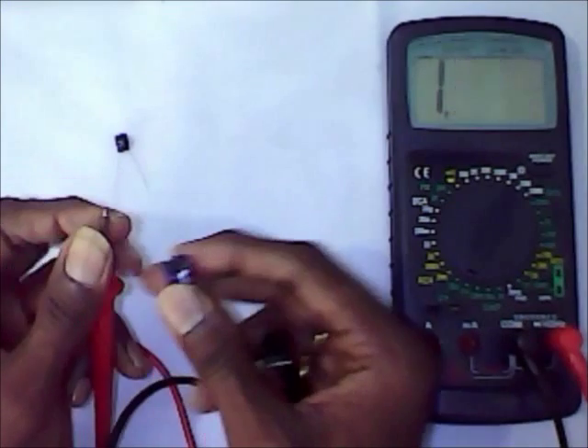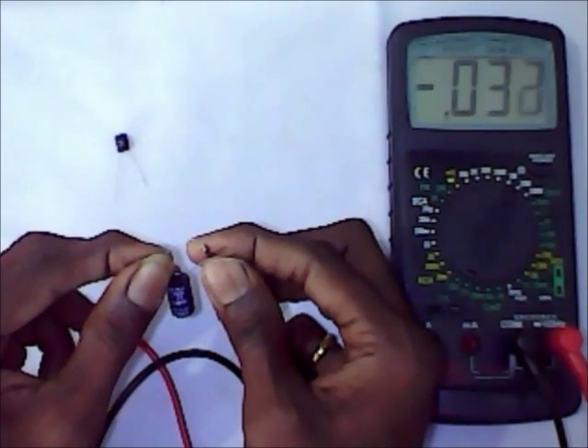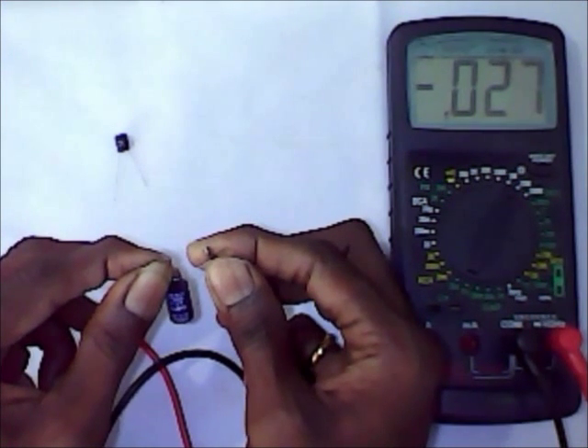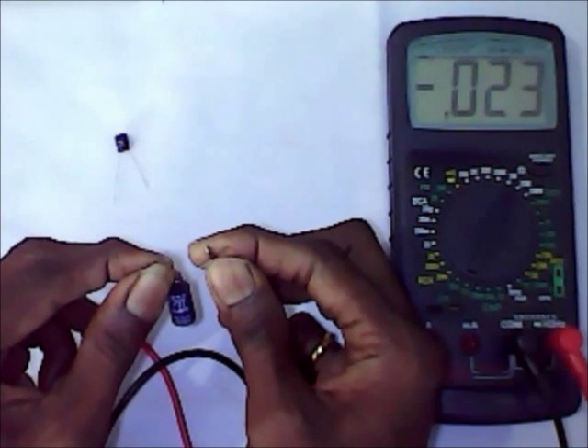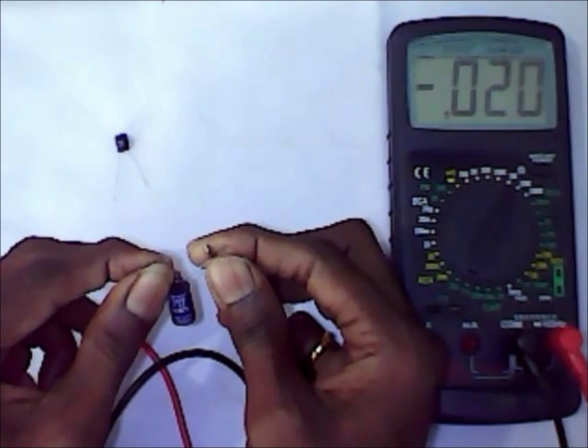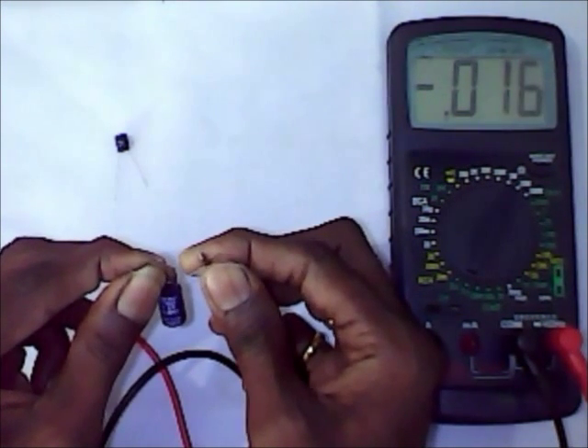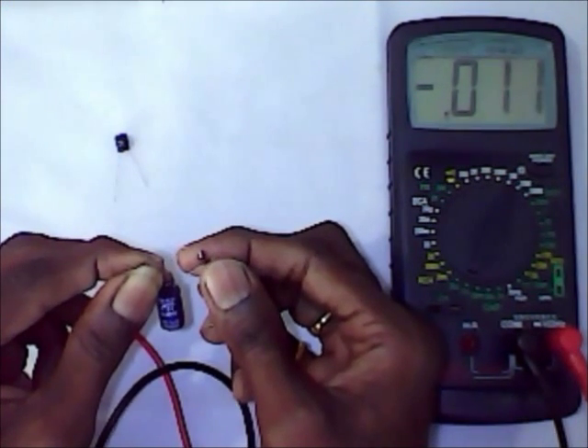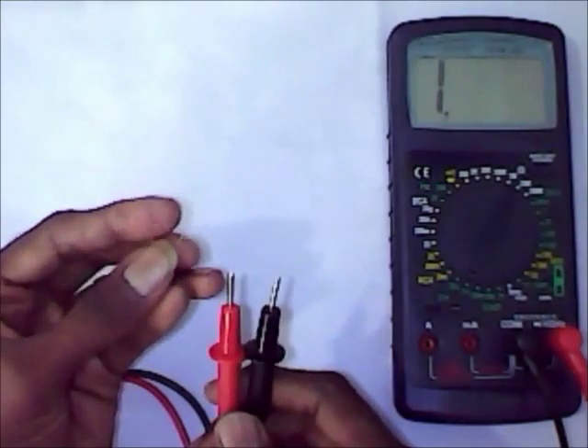Just reverse the terminals. The deflection should be higher first and it should lower down. It should go down slowly. It is going down. It indicates that the capacitor is in good condition because it charges in one direction and when we reverse the terminals, it discharges in the other direction. This is another capacitor.